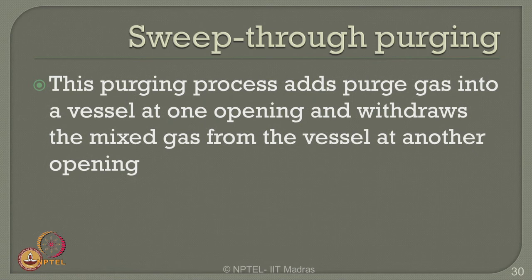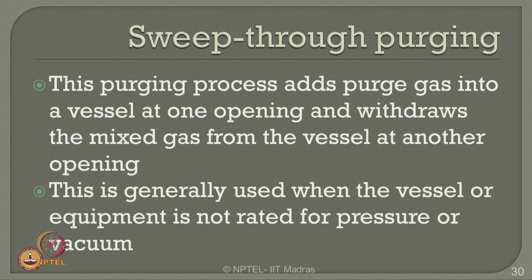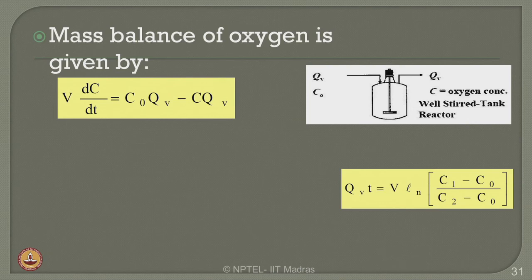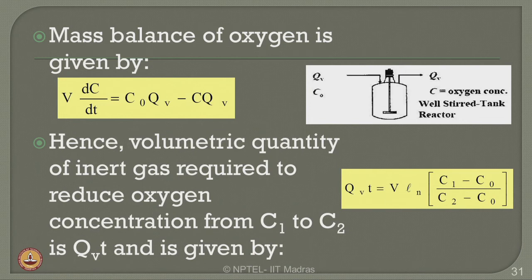One can also do sweep-through purging. This process adds purge gas into a vessel at one opening and withdraws the mixed gas from the other end. This is generally used when the vessel or equipment is not rated for pressure or vacuum purging. The mass balance of oxygen in this case is given by the equation in the slide. The volumetric quantity of inert gas required to reduce oxygen concentration from c1 to c2 is Q_vt as given by the equation.